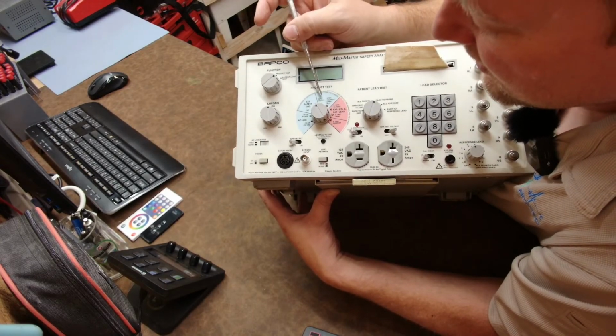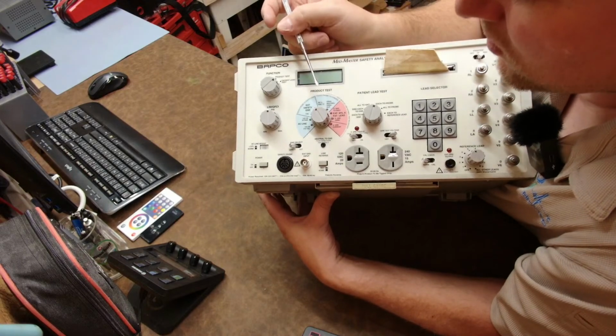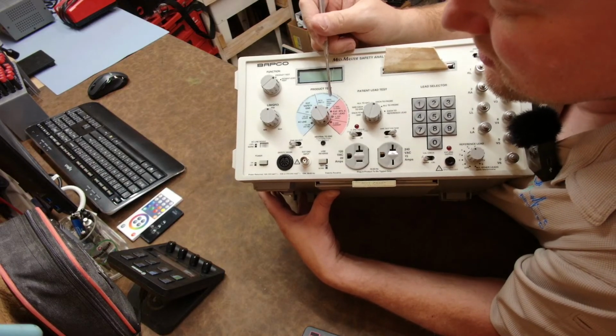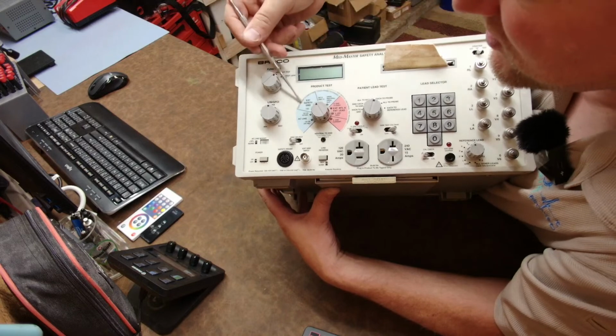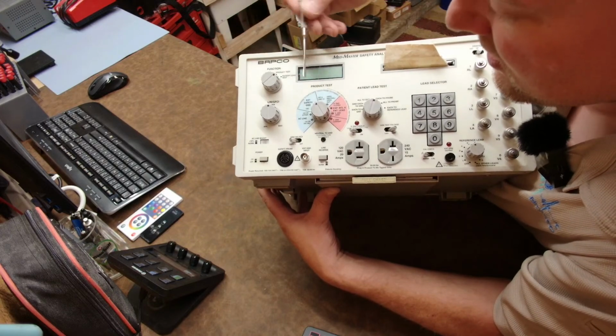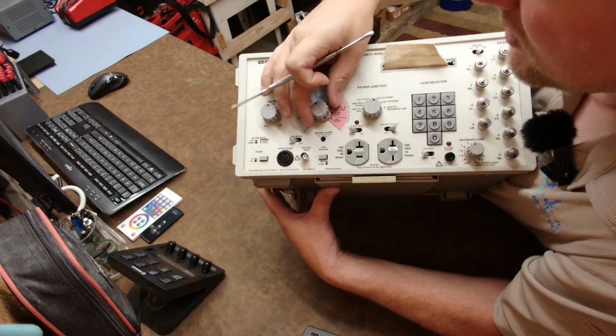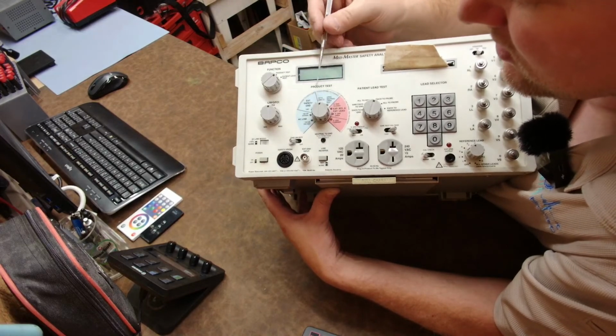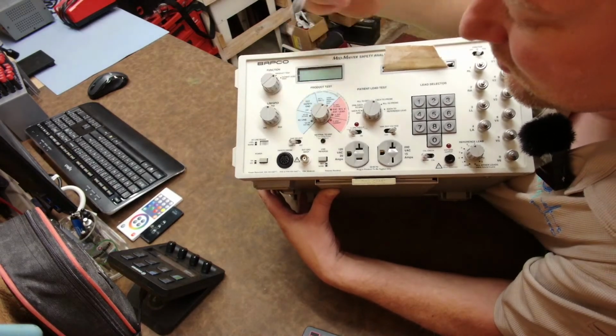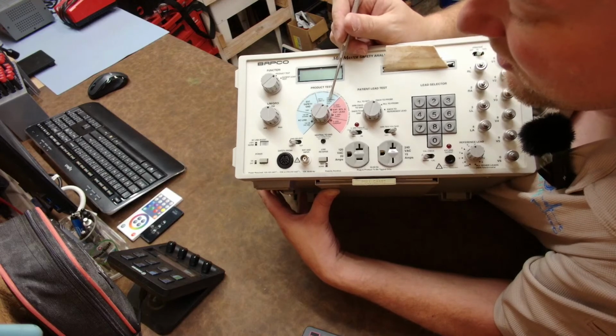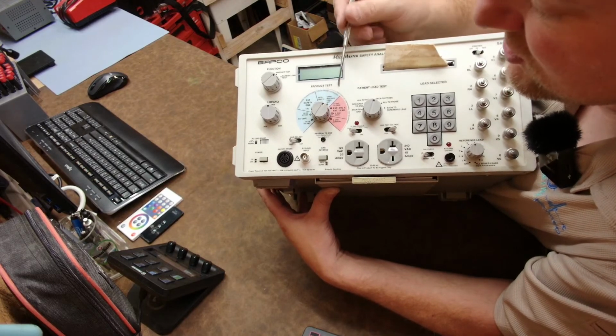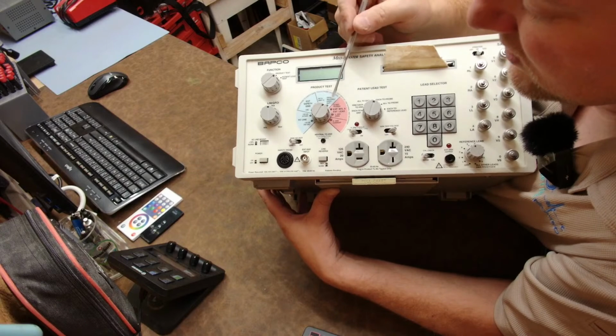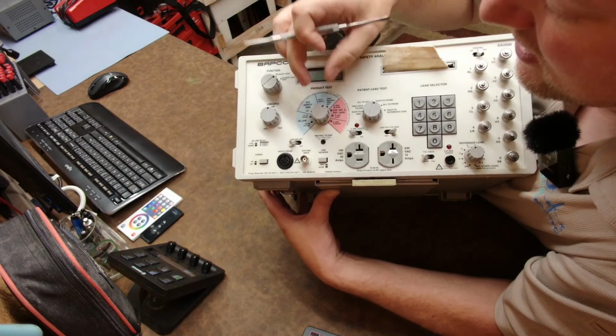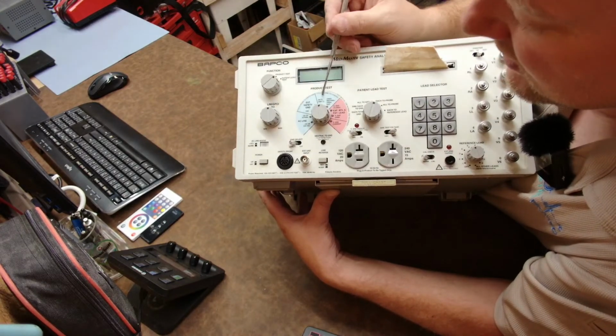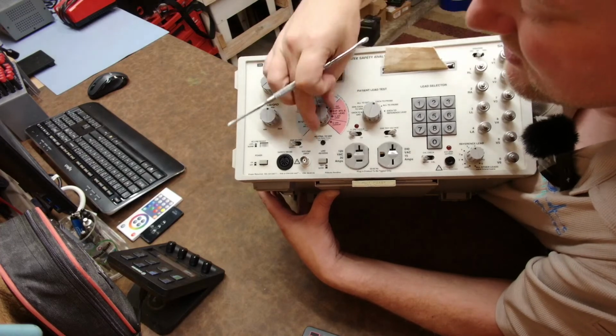So we have internal safety ground ohms, touch probe to chassis. Oh, earth ground, okay, so this section says touch probe to earth ground, touch probe to chassis. So we'd normally be doing the chassis ground. And let's see, we have open neutral, open hot. So this is just testing without your mains connected, and then you'd be doing it with mains connected.